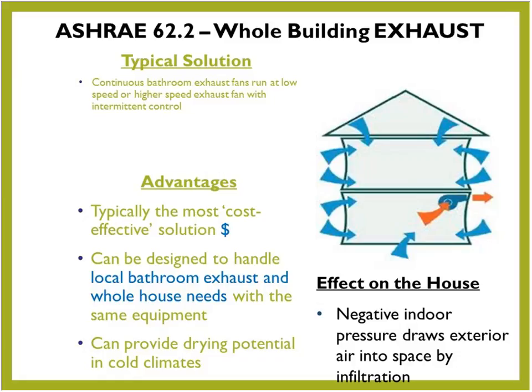So on the first slide here, on the three different types of ventilation, we've got the exhaust only strategy. And again, this is a bathroom fan or a kitchen range hood that's exhausting air to the exterior of the building, or, in the case of meeting your whole house ventilation requirement, a fan that's running somewhere in the home, either continuously at a low CFM or at a higher CFM on an intermittent basis, so that at the end of the hour you've extracted the number of CFM required to meet your code.